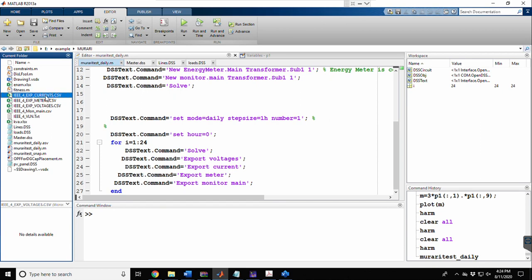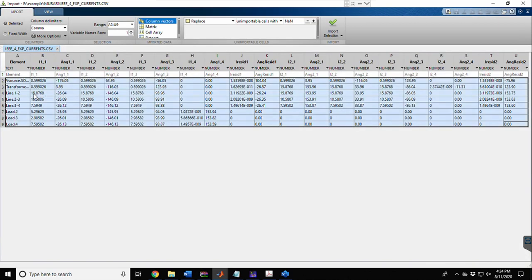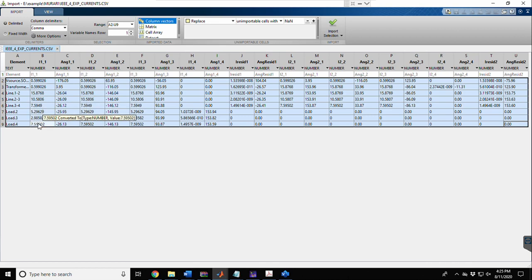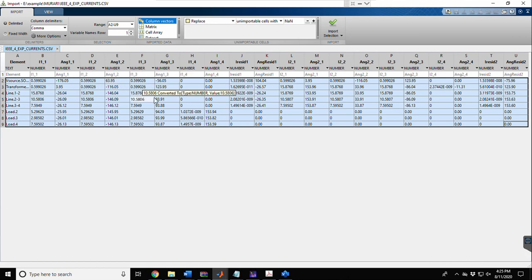Looking at the current export file: there are different elements — the source, the transformer, then lines 12, 23, and 34, and finally the loads showing how much current each is consuming. These are the current magnitudes. Since this is a balanced network, phases 1, 2, and 3 have the same magnitude but their angles are displaced by 120 degrees.